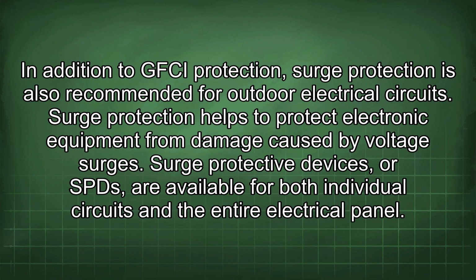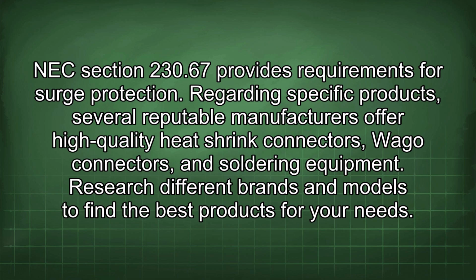In addition to GFCI protection, surge protection is also recommended for outdoor electrical circuits. Surge protection helps to protect electronic equipment from damage caused by voltage surges. Surge protective devices, or SPDs, are available for both individual circuits and the entire electrical panel. NEC Section 230.67 provides requirements for surge protection.